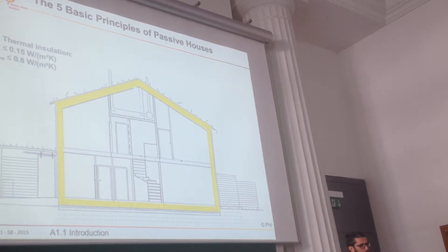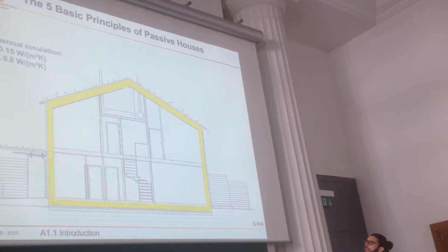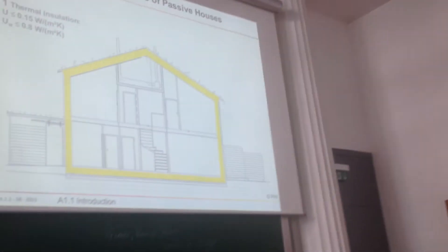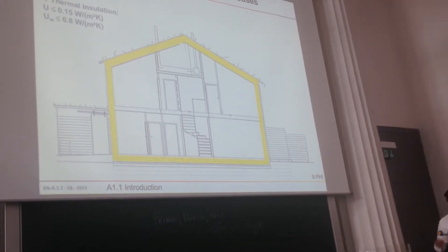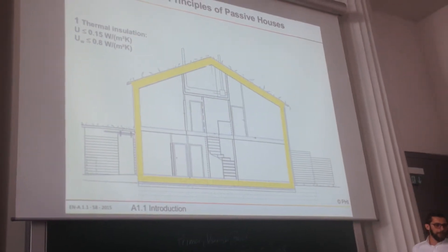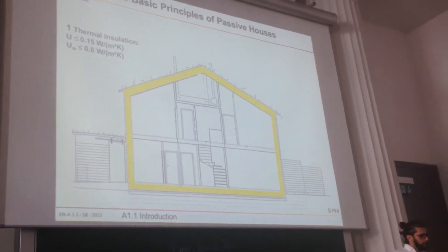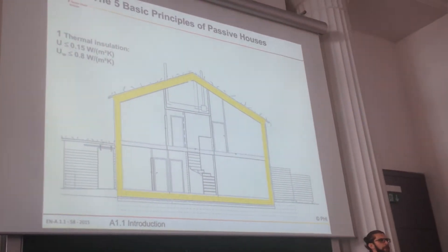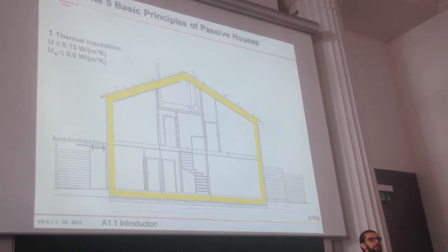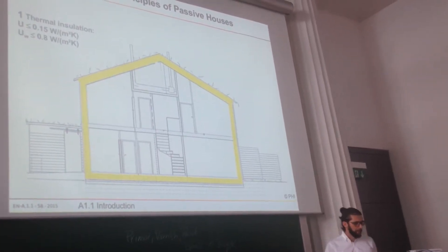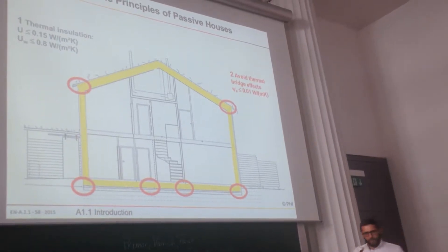Thermal envelope. We've heard already about the U-values. When we're talking about passive house standards for moderate climate zones, the U-value should be around 0.1 or 0.15 W/m²K. How many of you have already calculated U-values? That's good.